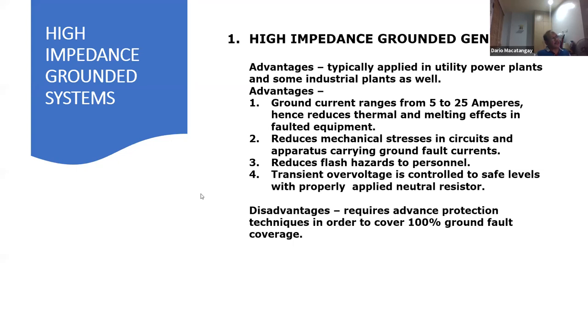What we normally do is limit the neutral current to 5 to 25 amperes, so we can reduce the thermal and melting effects in the faulted equipment. That's the advantage here. It will reduce the mechanical stresses in circuits and apparatus carrying ground fault currents, reduce the flash hazard to personnel, and reduce the transient overvoltage to safe levels because of the presence of the neutral resistor.